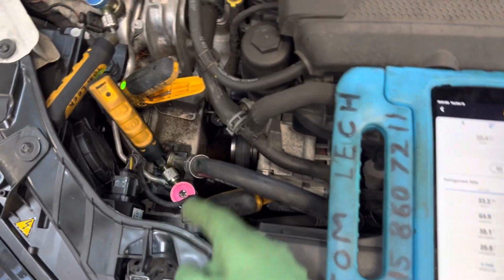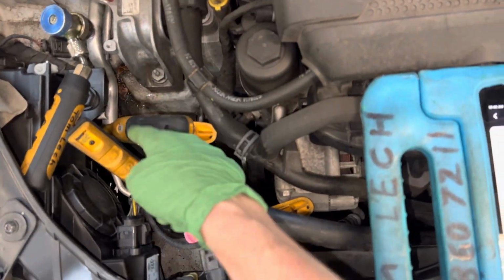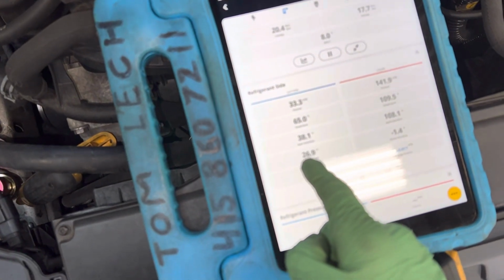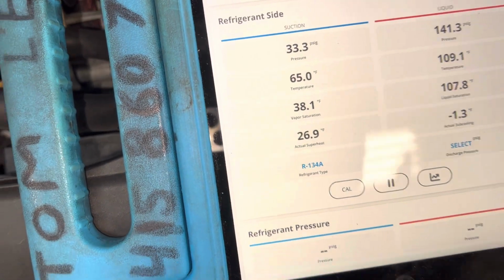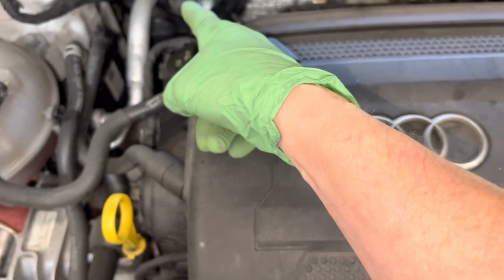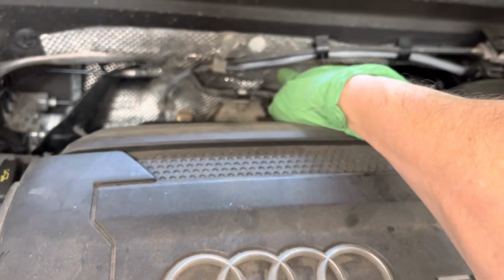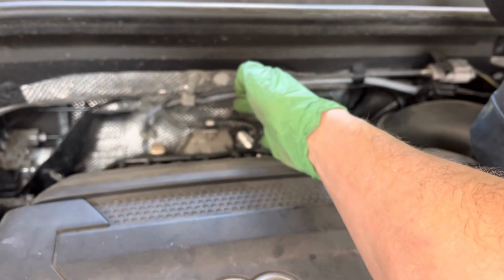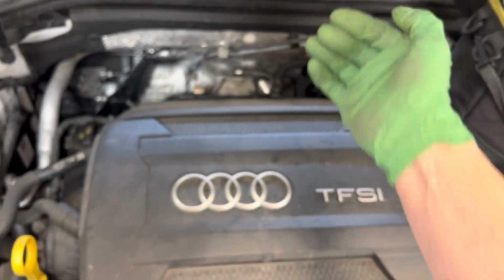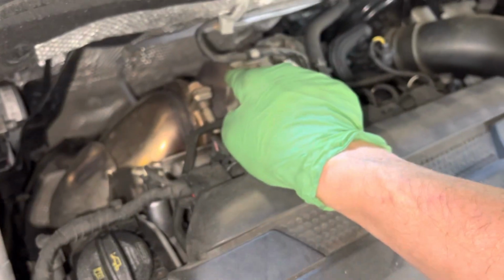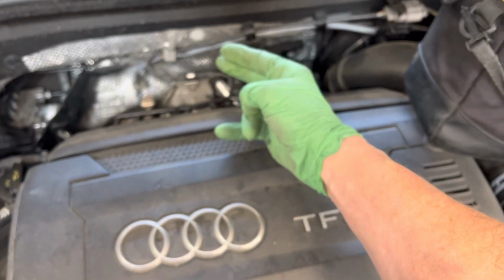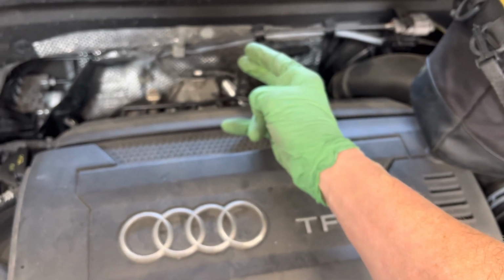Superheat is 26, 26.9 on this vehicle. There's an intercooler right there, the internal heat exchanger, but I cannot clamp it since it's back there, so I cannot clamp right after the evaporator. I also cannot take the temperature coming out of the evaporator because of the heat shield, since they have a turbocharger right there. So there's no way for me to put my temperature clamp directly on the outlet of the evaporator and take that temperature. There's very little places for me to connect to get my sensors on.